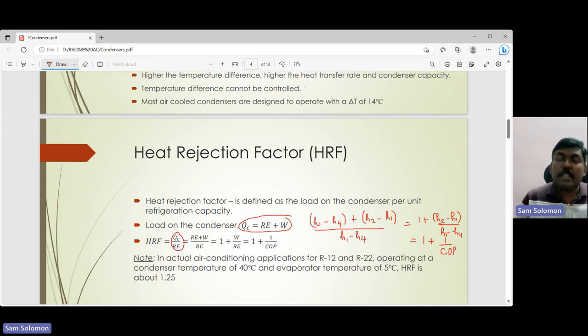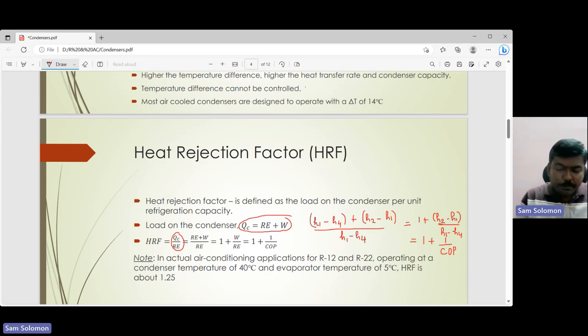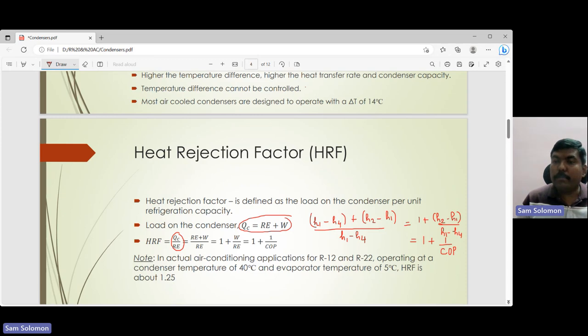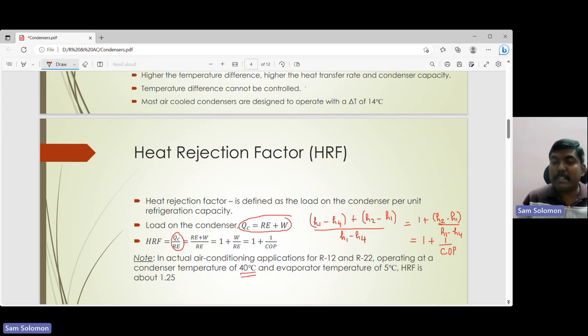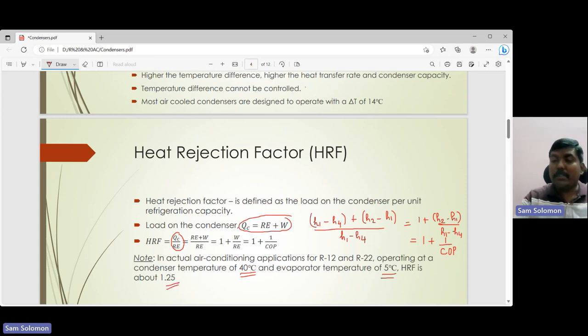So the heat rejection factor is 1 + 1/COP — a key terminology used in specifying condenser performance. As a practical note, in actual air conditioning applications using refrigerants R12 and R22, the usual operating temperature of the condenser is 40°C and the evaporator temperature is 5°C. In this scenario, the heat rejection factor is 1.25.